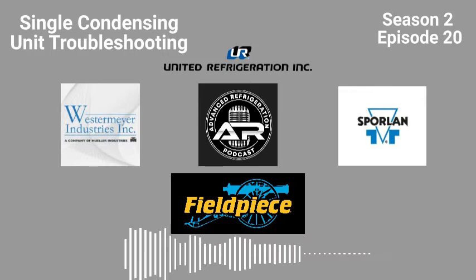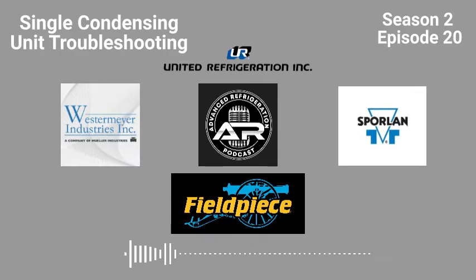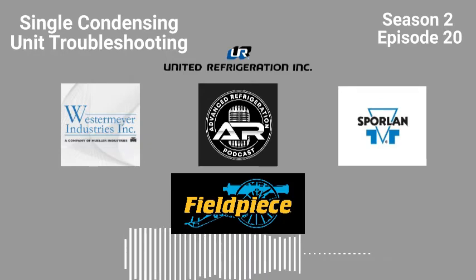So like the stores we had, the sizing wasn't as bad. Was yours a walk-in though, right? No, mine were cases. They were open grab and go cases, Hill cases. QC-R. Yeah. I'll tell you right now, those cases are more efficient than what Hill says. Which is unusual, but those cases, the coil TD was like 2 to 3 degrees at max. So they're more efficient than what they say, but this is the problem with putting these high efficiency cases on condensing units. It does not work.